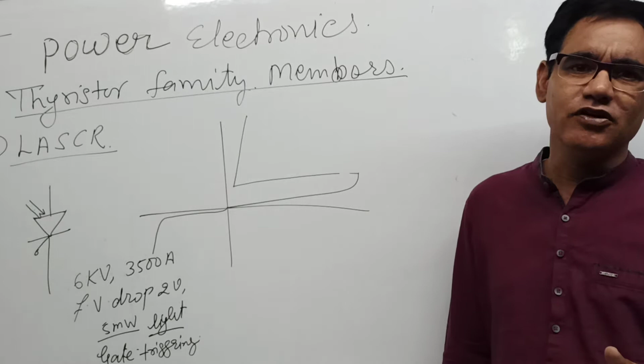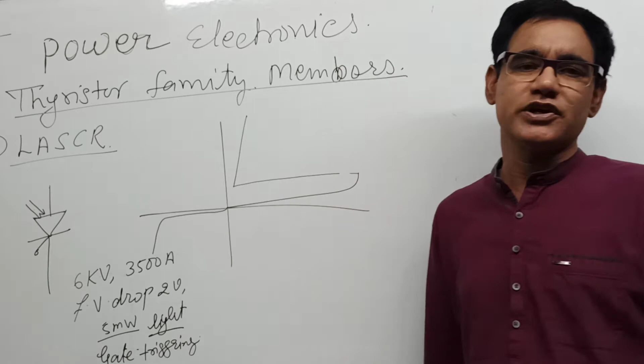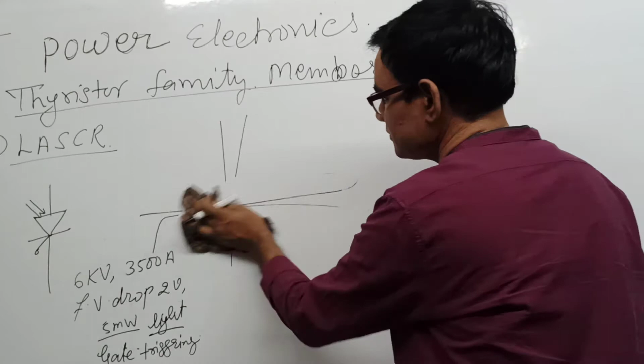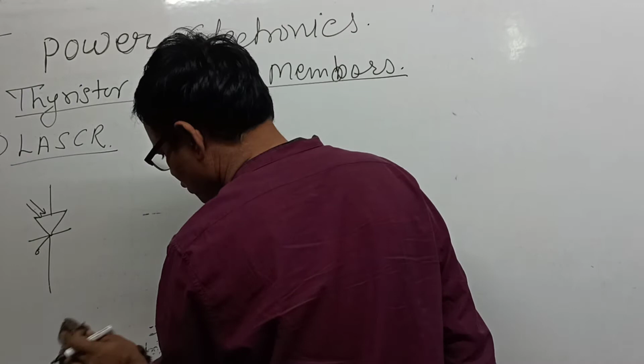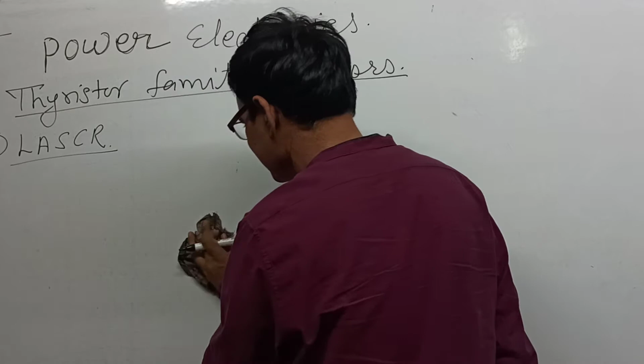LASCR is generally used in HVDC and extra high voltage applications. It requires a black box so that natural light does not fall on this device, only the intended light signal triggers it. This is somewhat costlier compared to a general SCR, so it's not used for general applications, but for special, higher rating applications. There is no danger of unwanted triggering because the gate is totally isolated - it is light triggered, not electrically triggered. So this is LASCR.